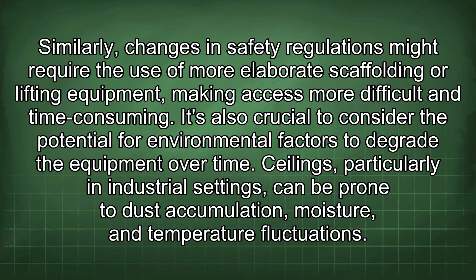Ceilings, particularly in industrial settings, can be prone to dust accumulation, moisture, and temperature fluctuations. These factors can accelerate the deterioration of electrical components and necessitate more frequent maintenance. In such cases, it might be prudent to choose a more protected location, even if it requires additional conduit runs or wiring.